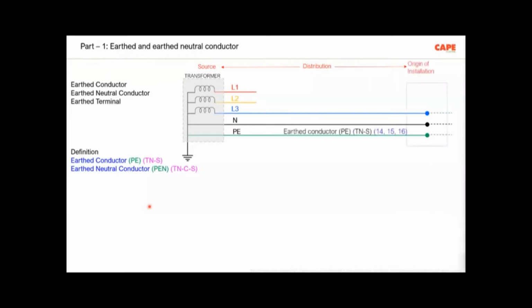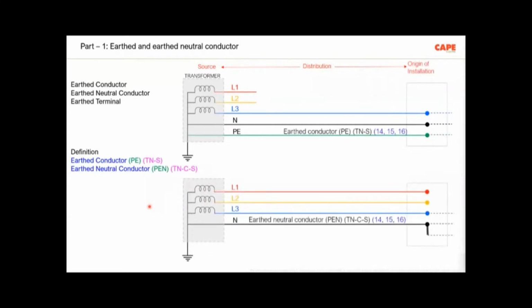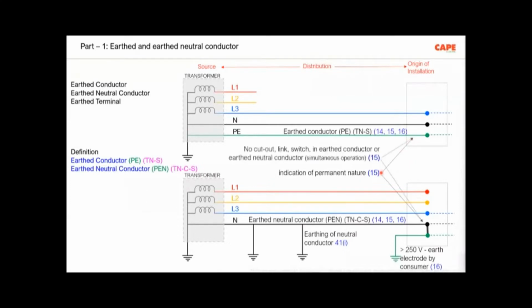We are supposed to get, for low voltage supply, a TN-S or a TN-C-S supply from the electricity supply company. Regulation 14, 15, 16 of the Central Electricity Authority safety regulations says the power supply company is supposed to give an earthed conductor, meaning a TN-S system, or an earthed neutral conductor to the consumer. Then they say this particular conductor, earthed neutral or earthed conductor, shall have an indication of permanent nature, and no cutout or link shall be inserted in this particular line. And then here, where I'm moving the cursor, the electricity supply company is supposed to give an earthed terminal to the consumer, meaning this earthed terminal is connected to the neutral of the power supply company through a metallic conductor.